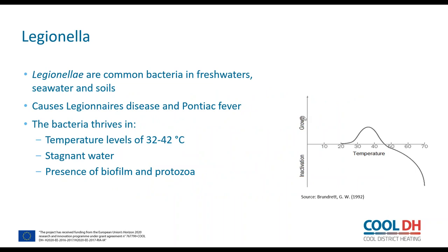Thank you. So first, what is legionella and why is it a problem? Legionella are bacteria that naturally exist in freshwater environments, but they have also been found in seawater and soils. Legionella can cause illnesses such as Legionnaires' disease and Pontiac fever. Legionnaires' disease is a severe variant of pneumonia, and Pontiac fever is a milder influenza. The comfort zone temperature level of Legionella is within the same range as the comfort level of domestic hot water. Legionella has an optimal growth rate at around 40 degrees Celsius. Legionella likes stagnant water and can be present in biofilm and protozoa, where conditions for growth can be even more suitable. In order to prohibit Legionella growth, national requirements on domestic hot water systems and temperature levels have been set, as Steen also showed. The temperature levels are set in order to avoid the growth of Legionella.